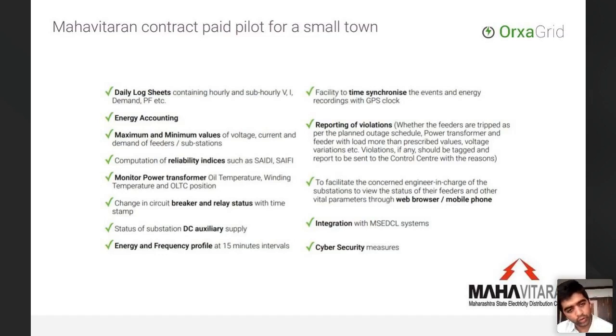We've implemented DI/DO statuses. Sorry, no output controls, only digital input controls were required. So that was to monitor power transformers, to monitor breaker and relay status, and understand what are breakdowns, what is manual load shedding, what are all the different classifications that come into place. Along with that, we've done a status of the station DC. So we actually monitor the DC voltage and current, and then alert the system operator in case the DC network fails in the substation, because the DC is most critical for ensuring that trippings and things like that happen on time.